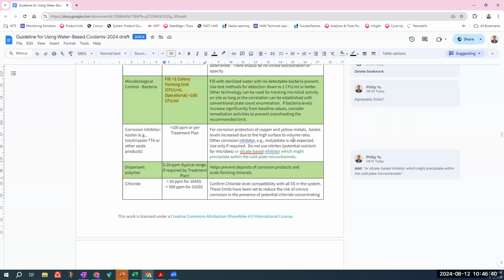It's not allowed to discharge to sewer. So if you have a molybdate-based corrosion inhibitor, you might want to pay attention to discharge regulation. Nitrite for mild steel protection is not recommended because it's prone to microbial degradation. A denitrifier can convert nitrite to nitrate and ammonia.